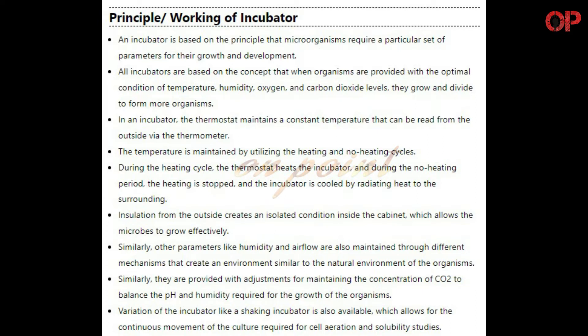Principle: An incubator is based on the principle that microorganisms require a particular set of parameters for their growth and development. All incubators are based on the concept that when organisms are provided with the optimal conditions of temperature, humidity, oxygen, and carbon dioxide levels, they grow and divide to form more organisms. In an incubator, the thermostat maintains a constant temperature that can be read from the outside via the thermometer. The temperature is maintained by utilizing the heating and no-heating cycles.